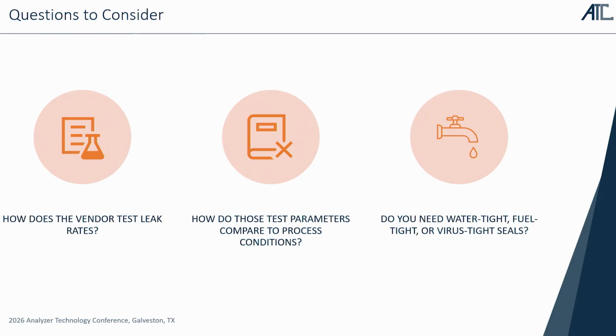So if you say, hey, I'm running at 200 degrees and I'm running at 500 pounds, I want to do a 2000 PSI hydro test on the probe to make sure that it's safe. Well, I don't know anybody that's going to do a 200 degree hydro test, right? So we're going to do a room temperature hydro test. What kind of derating or verification do you need to know that as you heat that up, it's still going to work, it's still going to hold as a seal? Do you need something that's actually virus tight, even though you need something that's technically watertight, to handle that derating due to the pressure changes?